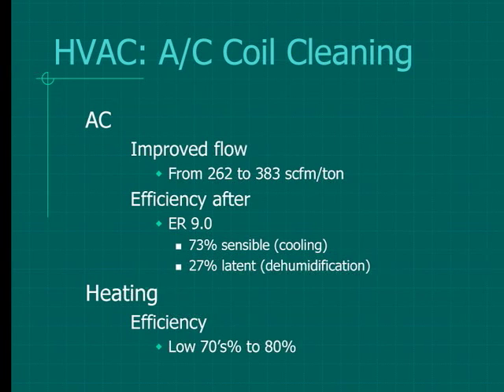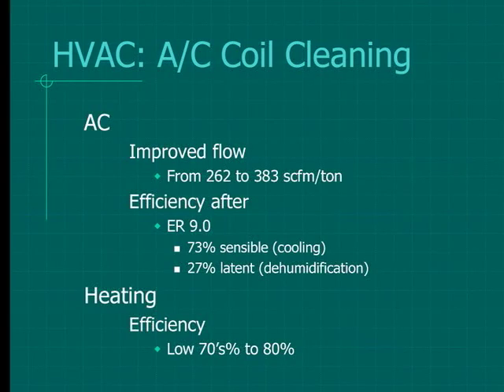The efficiency of this air conditioner is running at 9 energy ratio. It's designed to run at 11, so we didn't quite get it to where we'd like to see it. Again, it's a combination of the system still being a little bit oversized for the ductwork. Now the heating efficiency, remember we were saying that furnace was shutting down every minute and 45 seconds? My 80% furnace is running more like a mid-70s, the number came out 73%. Just by getting this air conditioning coil clean and changing the filter, we went from 73% to 80% on the furnace, and the air conditioner went up to 9 on the energy ratio. We're estimating it was about 6 before we did the retrofit here.